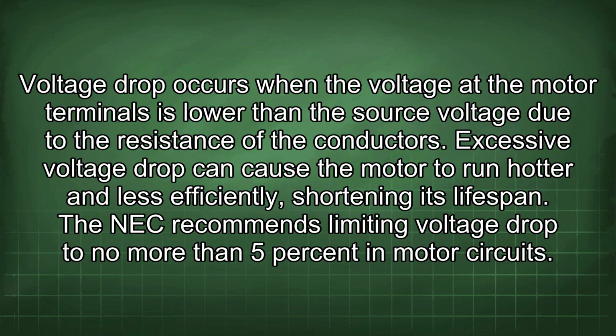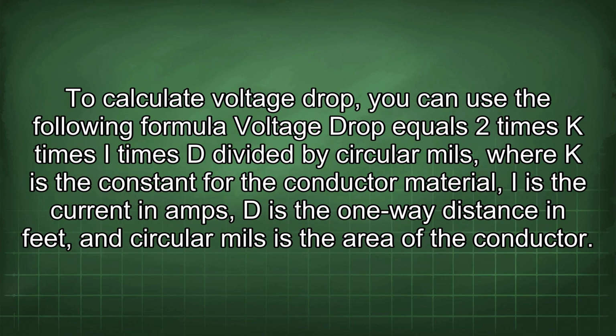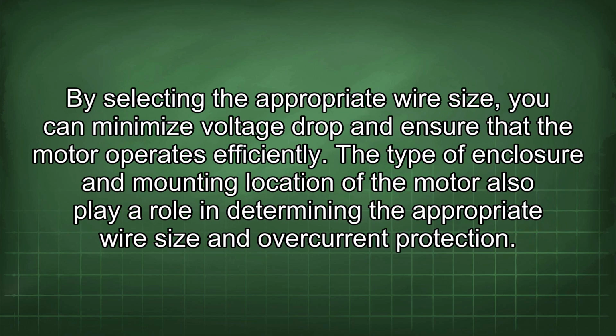Excessive voltage drop can cause the motor to run hotter and less efficiently, shortening its lifespan. The NEC recommends limiting voltage drop to no more than 5% in motor circuits. To calculate voltage drop, you can use the following formula: voltage drop equals 2 times K times I times D divided by circular mils, where K is the constant for the conductor material, I is the current in amps, D is the one-way distance in feet, and circular mils is the area of the conductor. By selecting the appropriate wire size, you can minimize voltage drop and ensure that the motor operates efficiently.